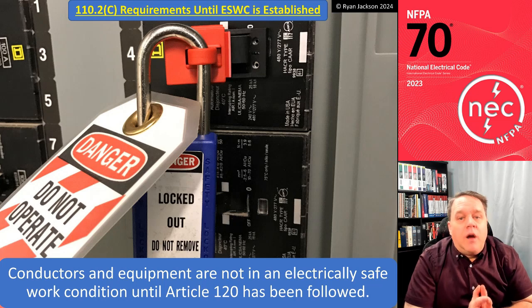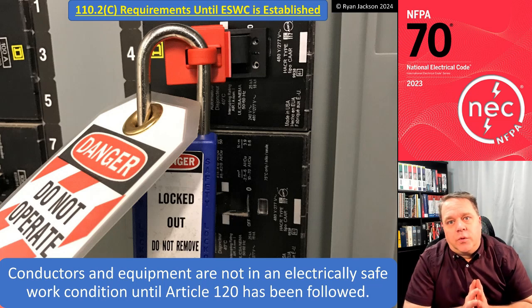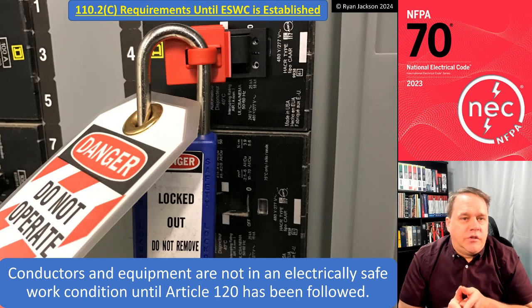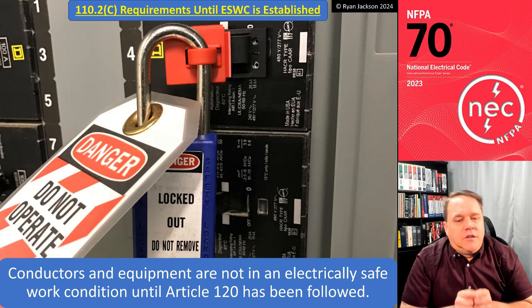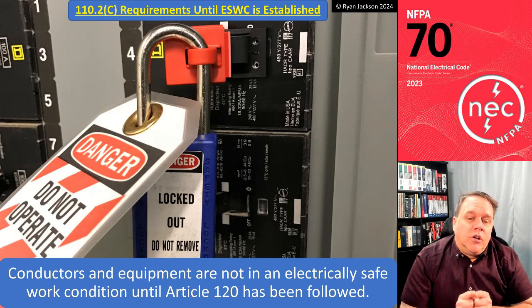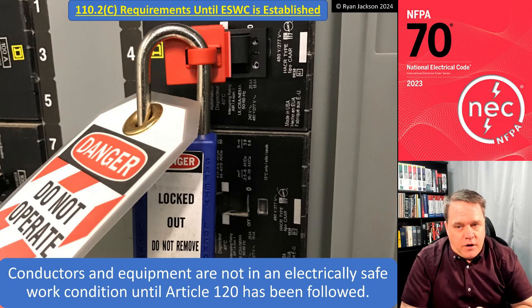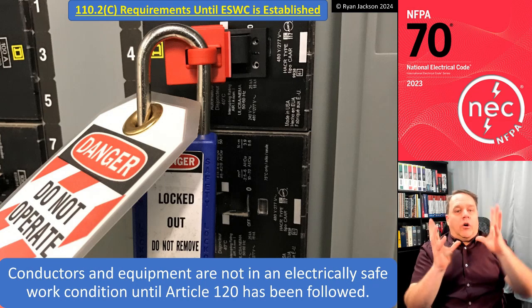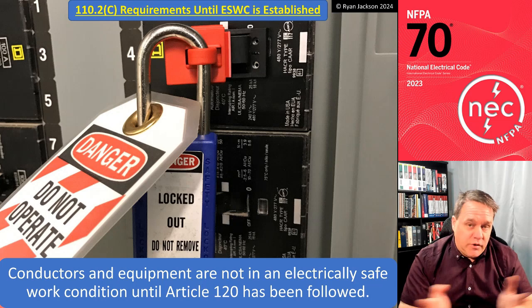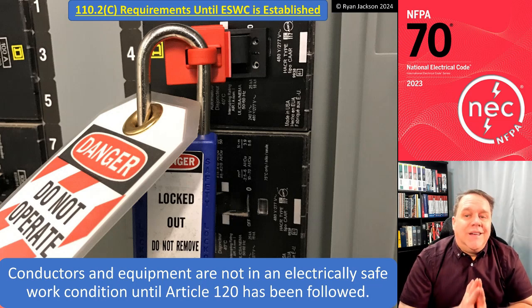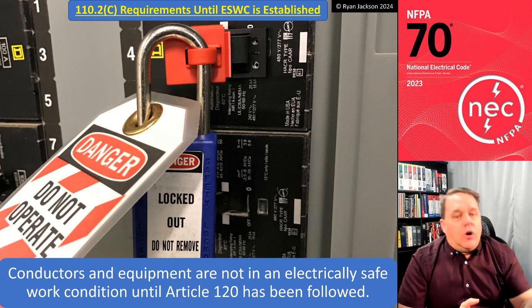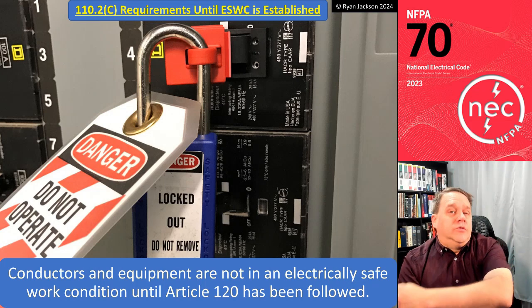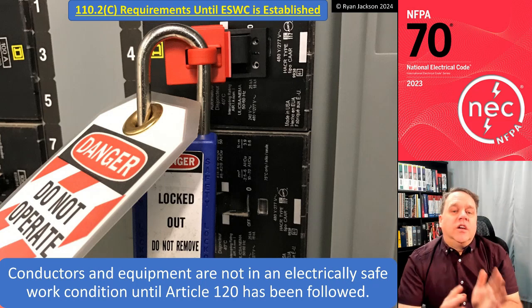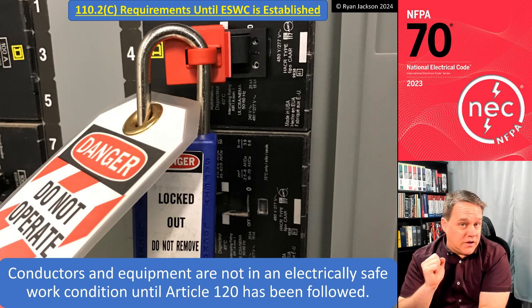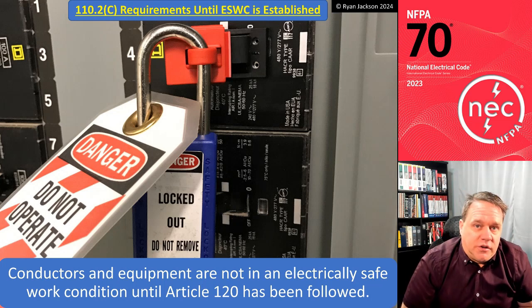110.2c, requirements until the electrically safe work condition is established. Conductors and equipment are not in an electrically safe work condition until Article 120 has been followed. All right. So Article 110, the section we're reading, tells you when you need an electrically safe work condition. Article 120 tells you how to create one. All right. And until you've gone through the entire process, you are not in an electrically safe work condition.